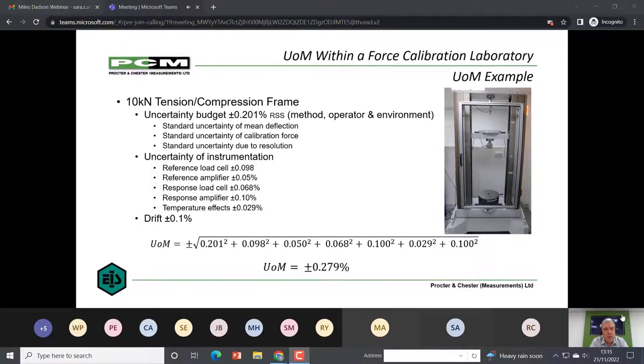And then you've got to add in all the instrumentation. First of all, you have a reference load cell, in this case just under 0.1%, and a reference amplifier, 0.05%. Then to assess the input force that you're using, you have a response load cell, 0.068%, and its associated amplifier, 0.1%. Temperature effects across a calibration, which within our calibration lab are of the order of 1 degree. Outside of that, you have to have greater control of the lab.